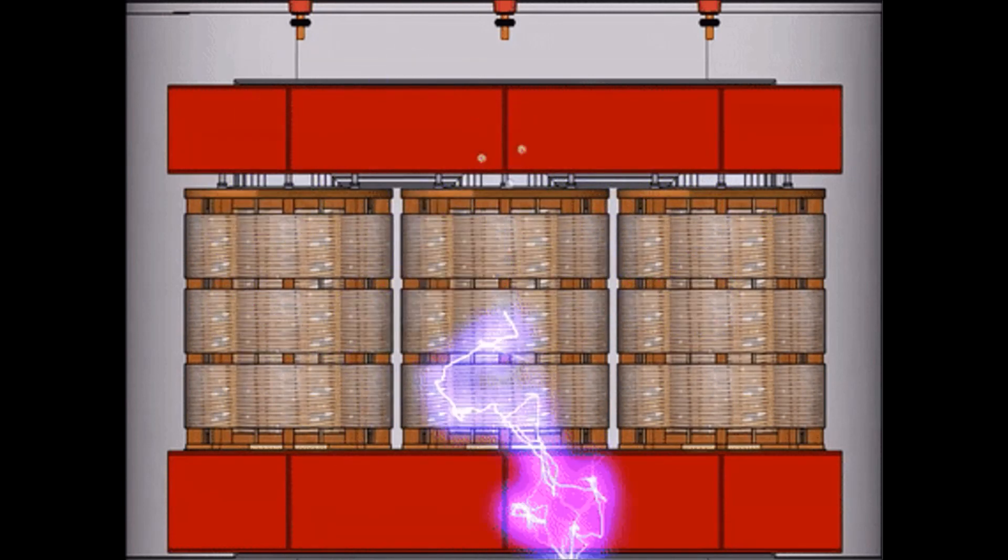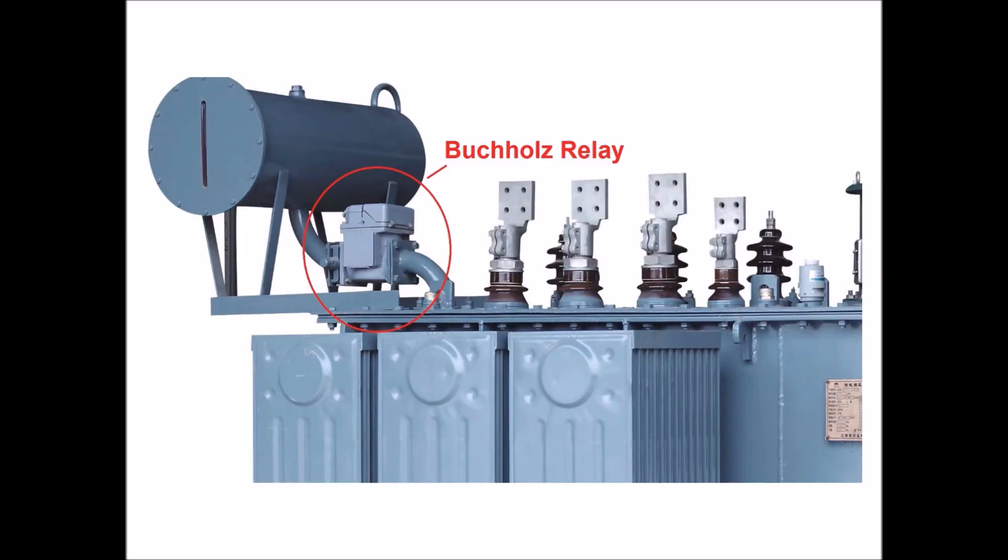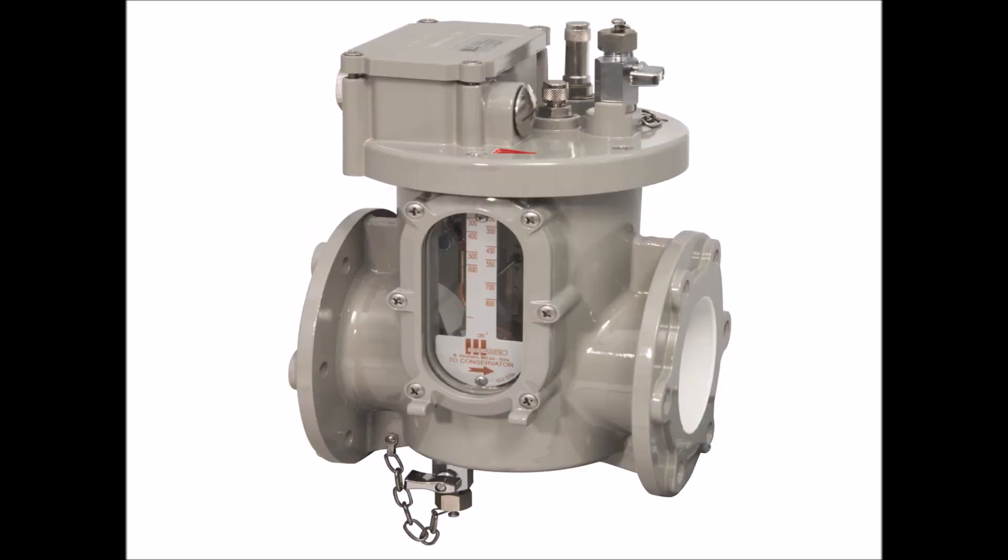Buchholz relay senses these faults and interrupts the transformer's input supply, so that greater damages may be prevented. Buchholz relay consists of an airtight external casing made up of aluminium, a terminal box fixed on its top, a viewing window to monitor oil level, and the gas release valve and test buttons at the top.